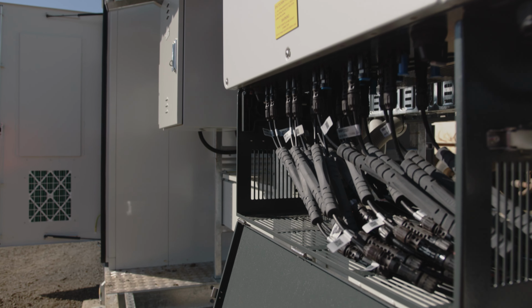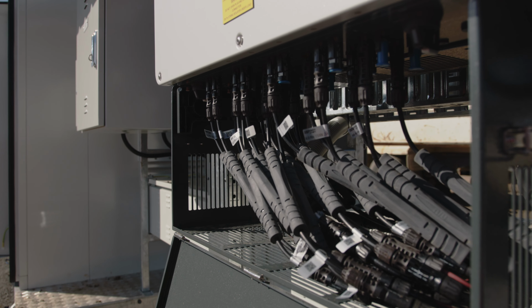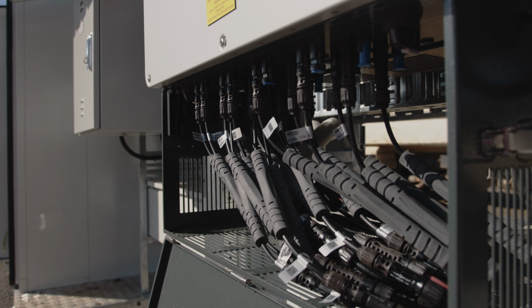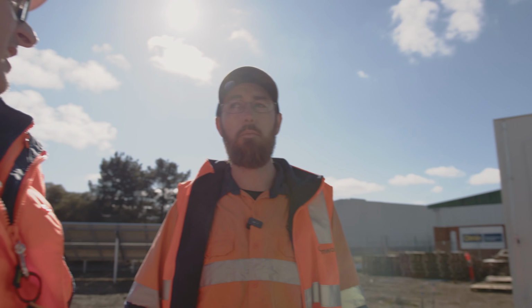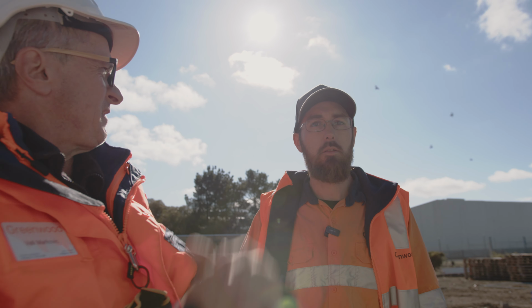Do we have fusing on the other end? We don't, and that's because there's no requirement. There's no paralleling out there. If we had the strings paralleled out in the field, we would put fuses out there to protect each string from the next one, in addition to the fusing here.